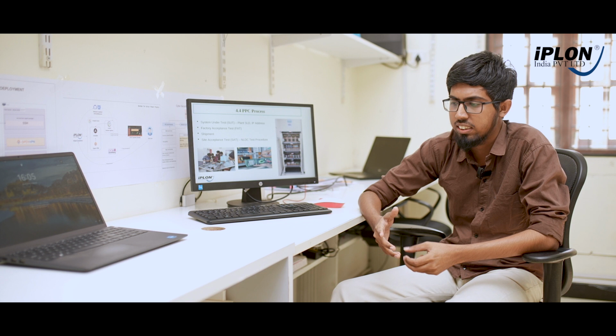Basically, first we prepare the quotation, and we send a person to the site. We do the site qualification test. We check if the site is capable for PPC, whether the inverter has the multi-client mode or not, and whether the inverter is capable of controlling active power and reactive power. The engineer tests all those things. After that site qualification test, if the site is capable for power plant control, then after the PO we have a certain process.